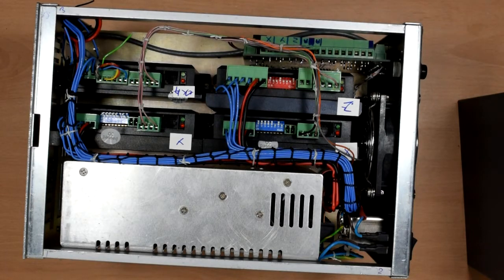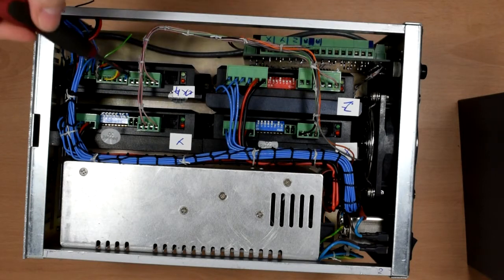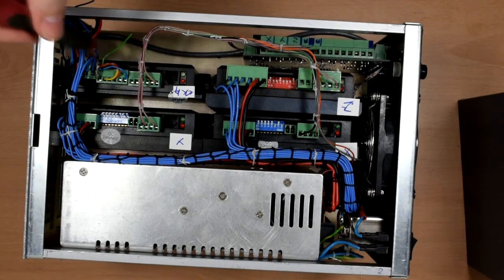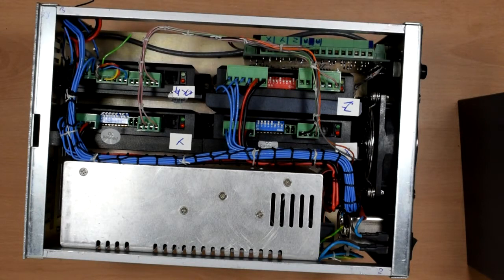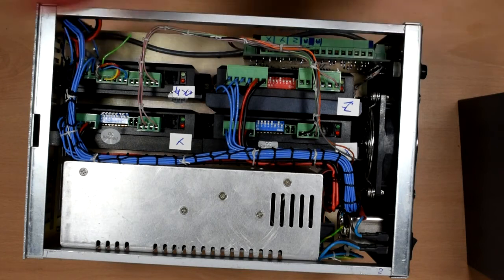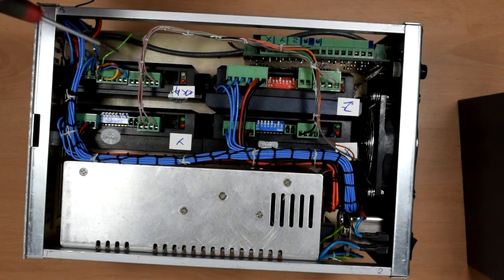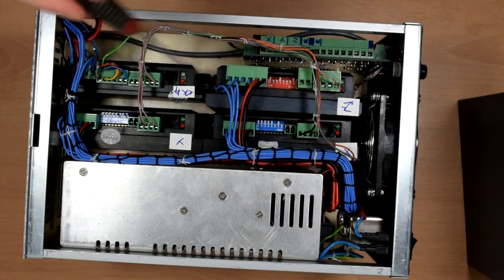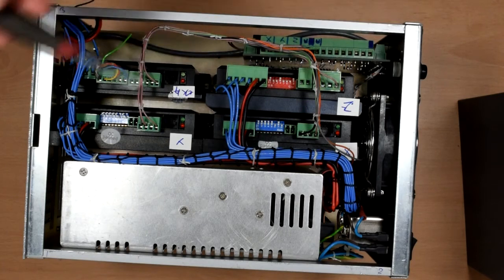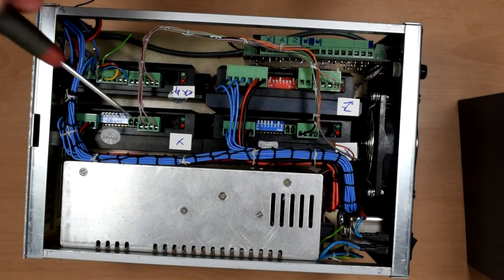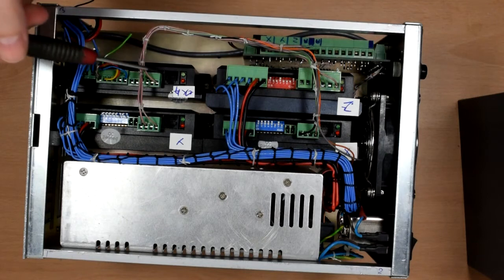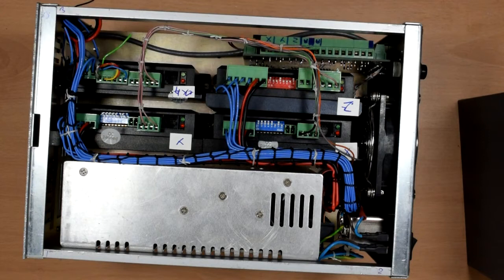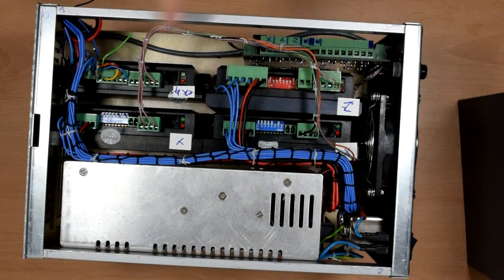And then I discovered that actually in order to tune the algorithms in this to your motor, there are various different parameters you need to tune. There's position tuning and current mode tuning, and the critical bit in the software that you need to tune this to a motor is password protected. So you don't actually need to use that function if you are using a LeadShine servo motor. But I wasn't. I was using one made by someone else and the function in the software that tunes it to third-party motors is password protected.